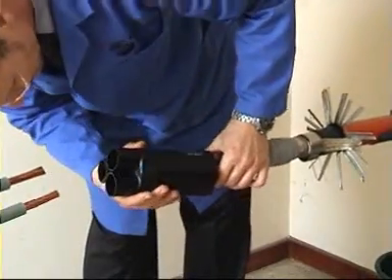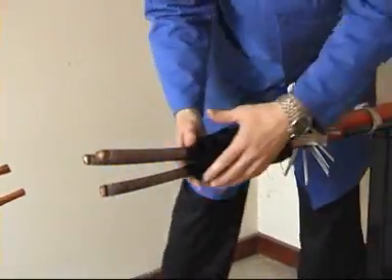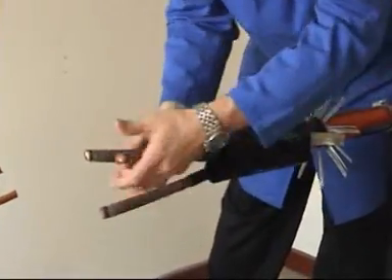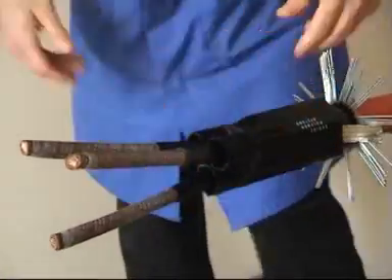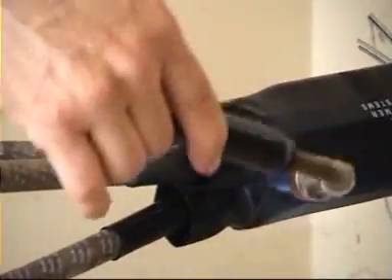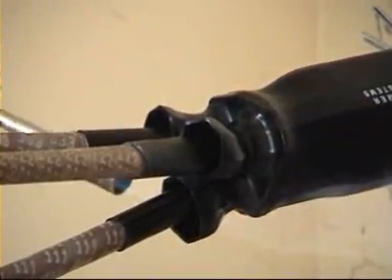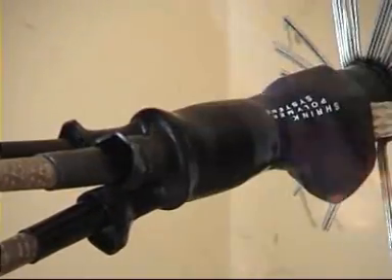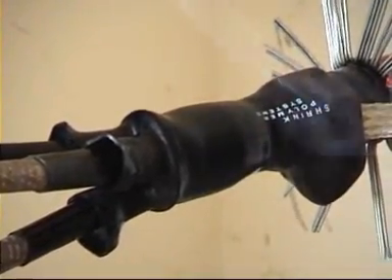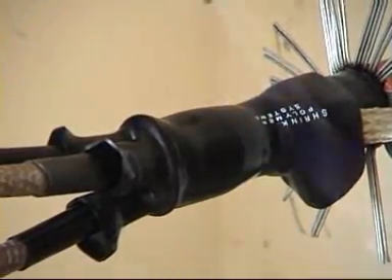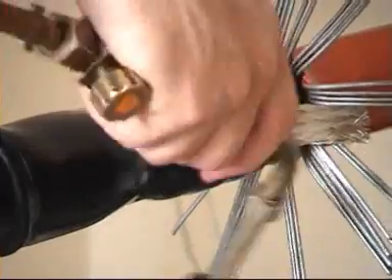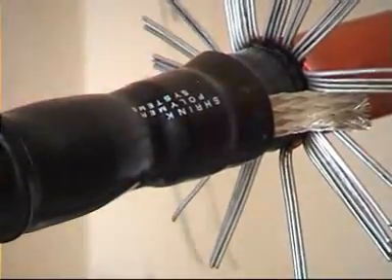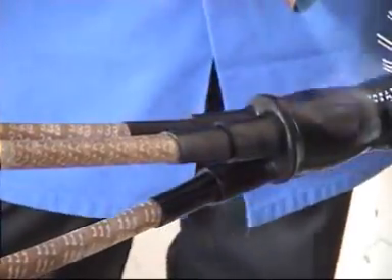Slide the three core conductive breakout over the cores and push well down into the crutch. Start by shrinking from the middle of the breakout, shrinking the skirt down to the lead sheath and then the legs to the cores.